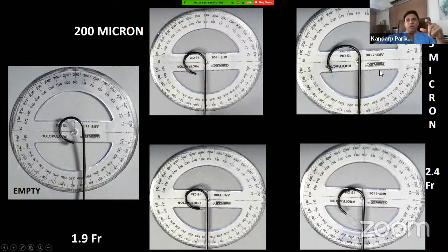This is 200 micron. When you put in a 265 micron fiber, you can appreciate that the deflection is compromised to a greater degree. Now it has come to 230, 240 degrees. So when the larger caliber laser fiber is in, the deflection is compromised. When you operate in a lower calyx, it's a good idea to use a 200 micron laser fiber rather than a larger one. Similarly, for baskets, if you put in a 1.9 French basket, that's my favorite, you can have almost 270 or 260-degree deflection, so there is no compromise. But when you put in a 2.4 French basket, you can see here the deflection is 230 to 240. So deflection is again hampered. This is also very important in choosing the accessory when the stone is located in a lower calyx.